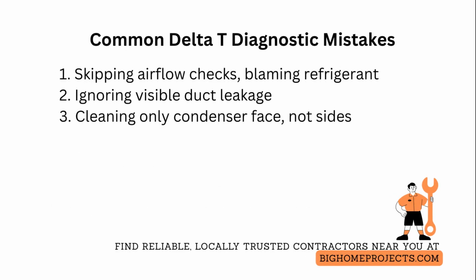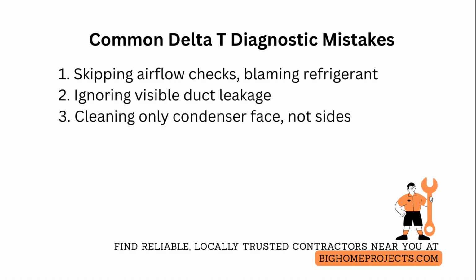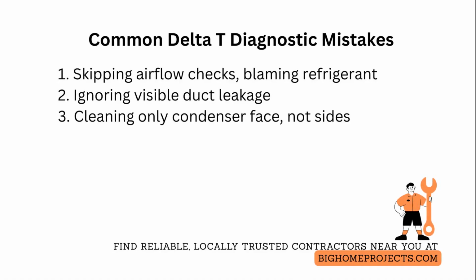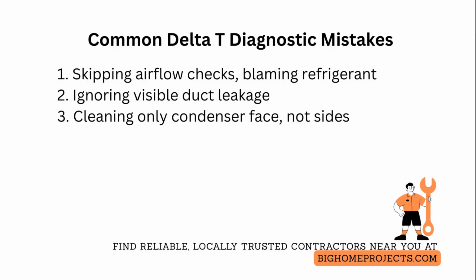One of the most common mistakes with abnormal Delta T diagnostics is skipping airflow verification and blaming refrigerant charge. Airflow issues from dirty filters, matted evaporator coils, or duct restrictions cause low evaporator load, leading to low suction pressure and frost that mimic undercharge.